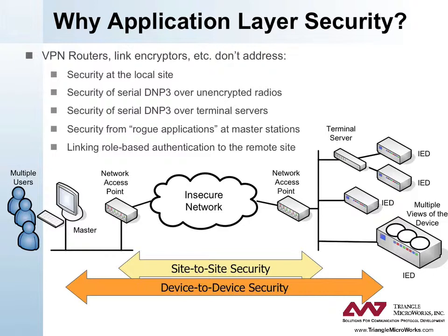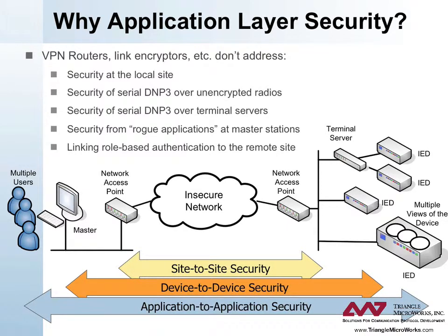Device-to-device security includes the use of protocols such as Transport Layer Security (TLS) to secure the complete TCP connection between two devices, similar to when you access your bank through the internet. However, TLS only works on IP networks and is therefore lost if DNP3 messages are forwarded over radios or serial links. It also does not address the possibility that rogue software applications may be installed on a device, making use of the fact that the device itself is considered secure. Application-to-application security ensures that individual users, not just devices, are authenticated by the remote devices, and that the authentication information will be carried wherever the DNP3 message travels. It permits remote outstations to perform role-based authentication and authorization, so that the level of security changes depending on who is attempting to perform an operation.